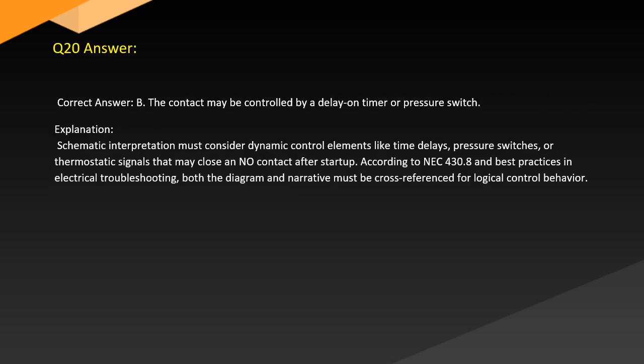Answer. Correct answer: B. The contact may be controlled by a delay-on timer or pressure switch. Explanation. Schematic interpretation must consider dynamic control elements like time delays, pressure switches, or thermostatic signals that may close a normally open contact after startup. According to NEC 430.8 and best practices in electrical troubleshooting, both the diagram and narrative must be cross-referenced for logical control behavior.